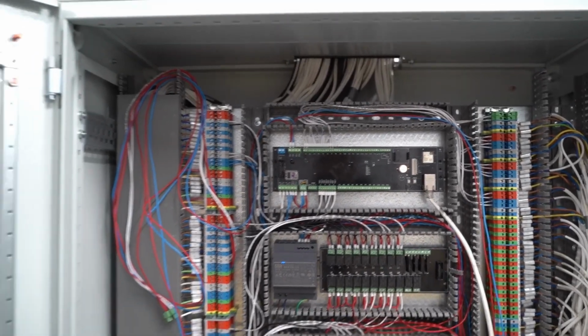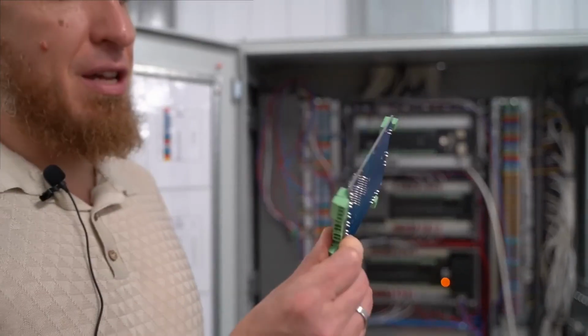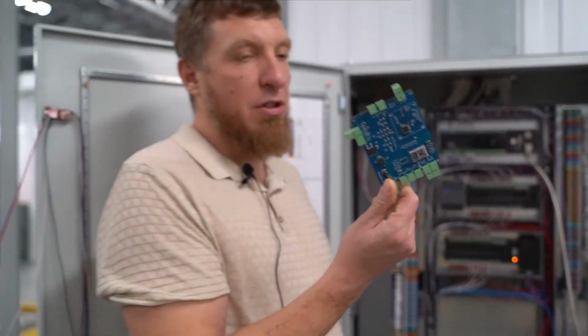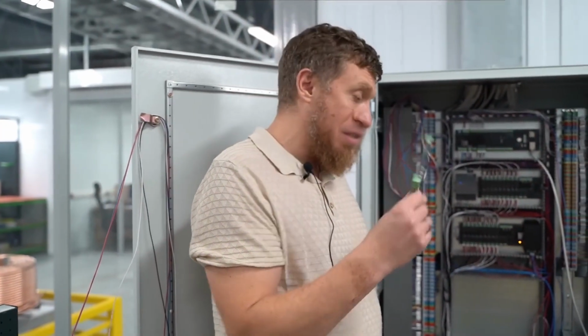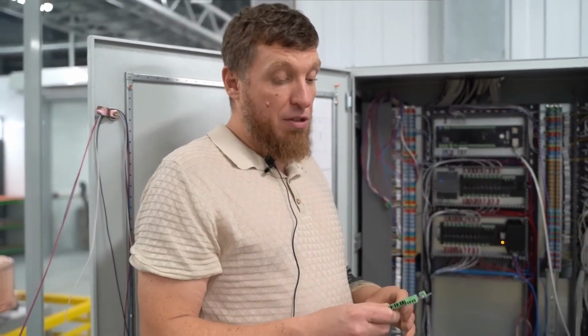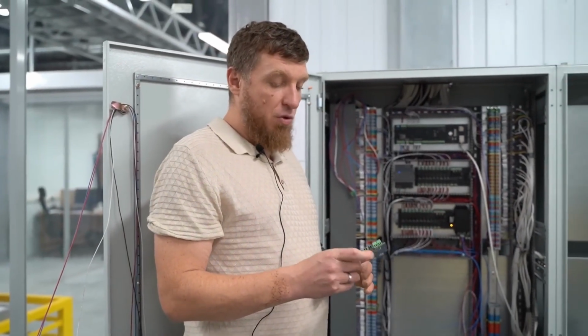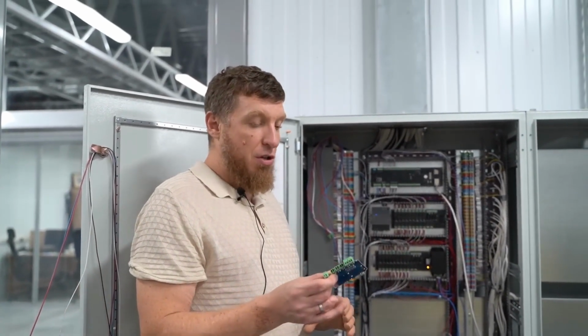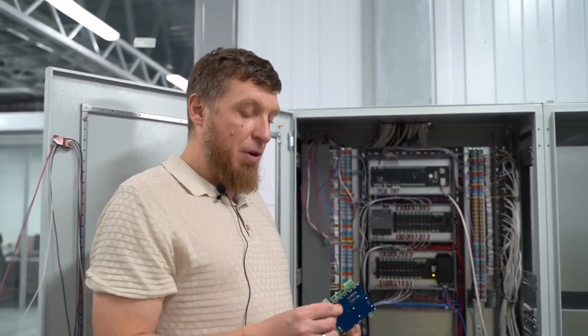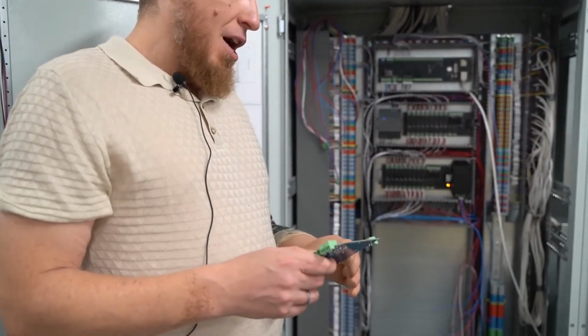Here is what our RVM control board looks like. This is from an old type, like a heat pump controller, of which there are many. We ordered the rest, and here it is. It can control 1 RVM, 4 or 5 via wired connection. There is a 4 to 20 milliamp input and a separate pressure sensor as well as temperature sensors. There will be 16 of them installed here.